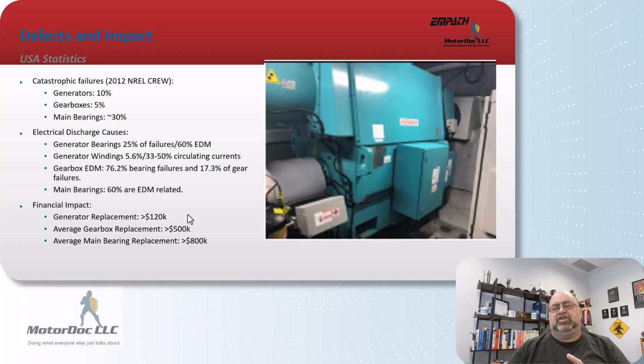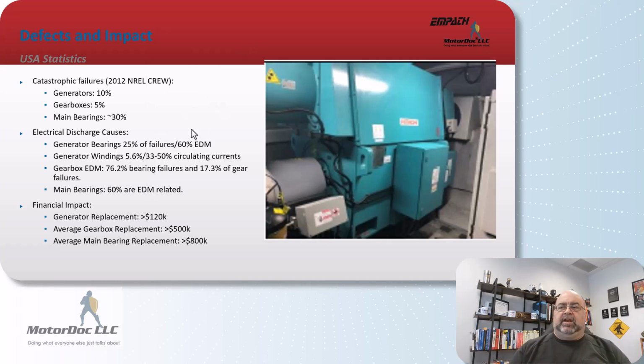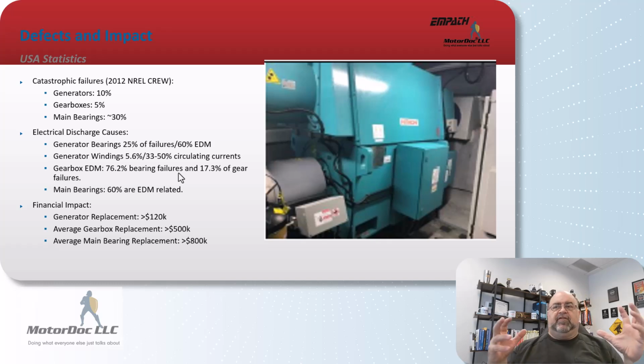Catastrophic failures, 10% of generators would see it. Gearboxes, 5%. Main bearings, about 30%. Main bearings, just to put that into perspective, you can look down here, the costs associated with each. These are the minimum costs, not the average, actually. Now, what was interesting is all of these had to do with electrical discharge machining, and it was during a separate study that we noticed that we had high circulating currents up tower. That led into future work and investigation.